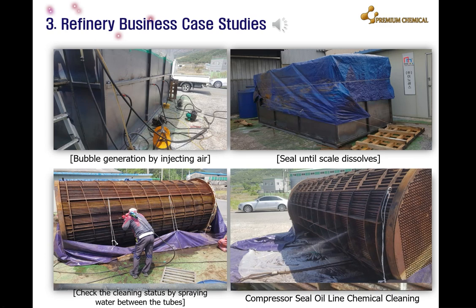Half of the bundle is immersed in the tank, sealed, and stored for 7 days until the butadiene scale dissolves. Once cleaning is complete, the bundle is rotated and placed back into the tank to immerse the remaining half. The tank is then sealed again and stored for 7 days to complete the chemical cleaning.